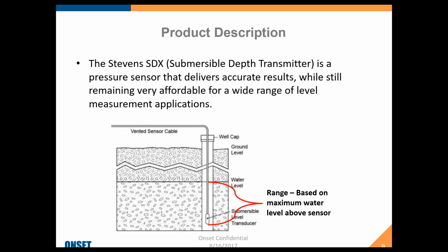This gives you an illustration of how you're going to measure or consider the water level range. It's basically the distance above the sensor to where the water level is expected to reach. That will give you an idea of the depth you need, as well as the cable length for the sensor. So there are 2 parameters you need to know when ordering the sensor: the depth it needs to be calibrated for, and the cable length you need to mount the sensor.